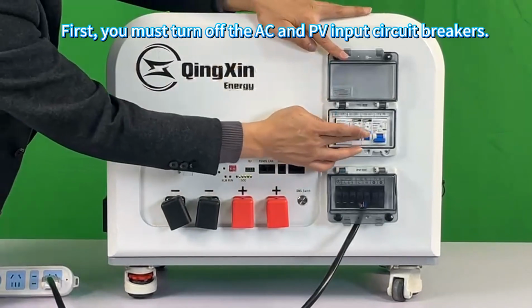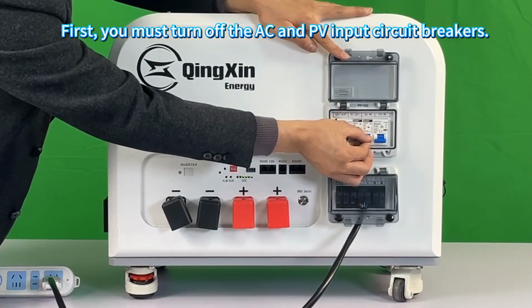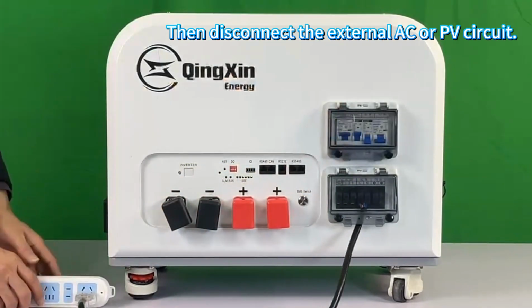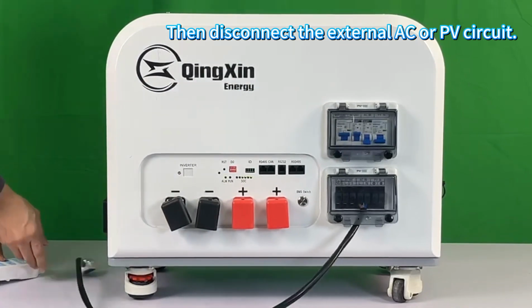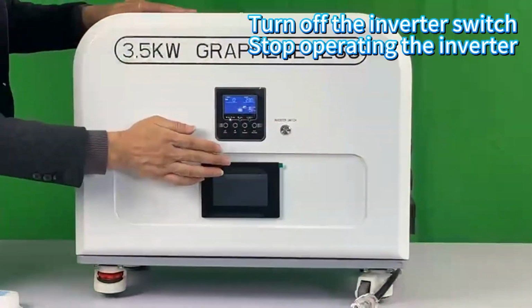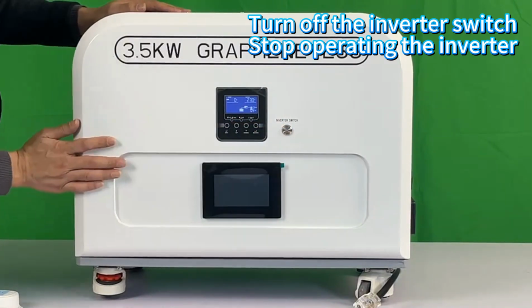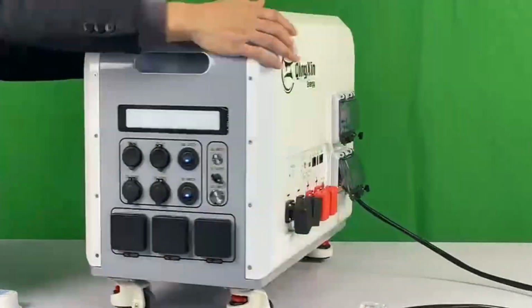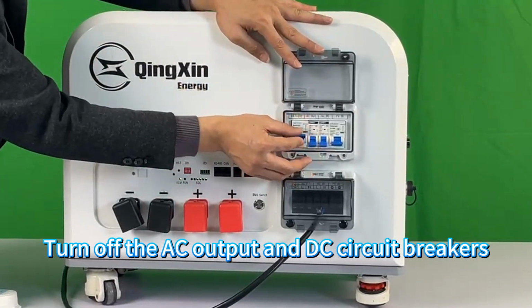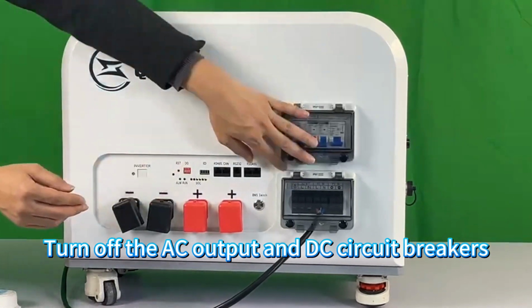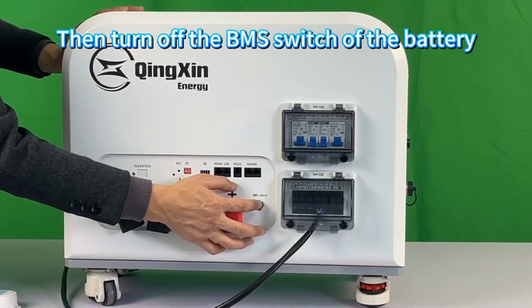First, you must turn off the AC and PV input circuit breakers, then disconnect the external AC or PV circuit. Turn off the inverter switch to stop operating the inverter. Turn off the AC output and DC circuit breakers, then turn off the BMS switch of the battery.